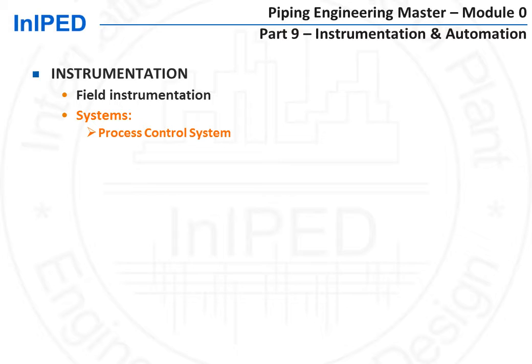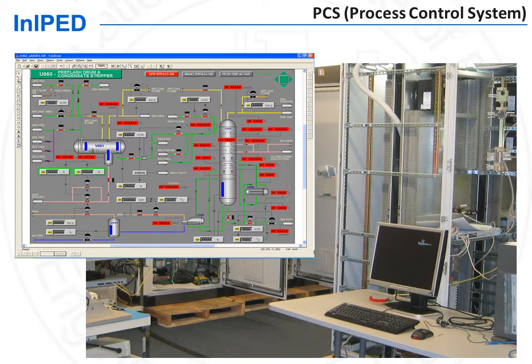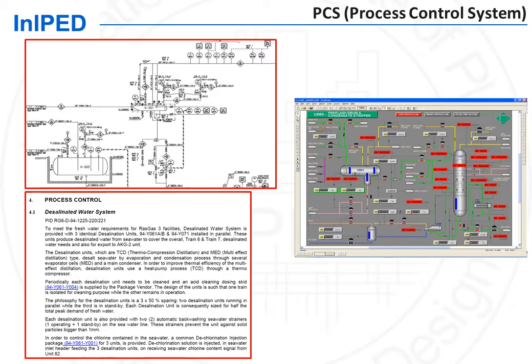Another work stream of this discipline is the systems — first of all, the process control system. The process control system functionalities are entirely defined by process, by means of two documents: the P&IDs, which show the process controllers and all instruments that are part of the process control system, as well as control narratives or functional analysis, which explain the control functions to be implemented. The application software is developed based on these two documents.